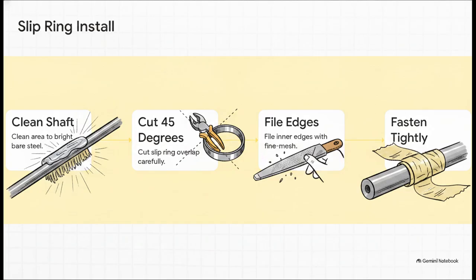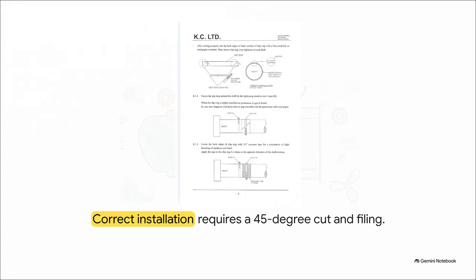Second, they cut the slip ring overlap at an exact 45-degree angle. Third, they file the inner edges with a fine mesh file or sandpaper. And finally, they fasten the whole assembly incredibly tightly around the shaft using a stainless steel band and layers of pressure tape, which actually has to be wrapped in the opposite direction of the shaft's rotation so it doesn't loosen up. And this brilliantly illustrates why those steps matter so much.